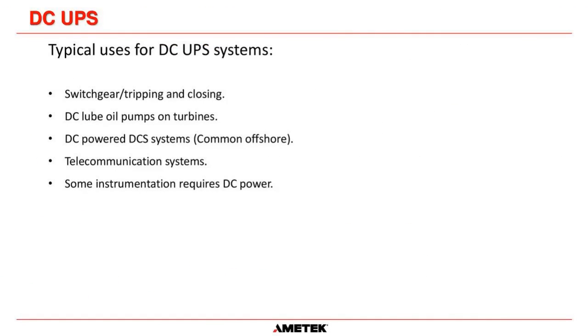So what are the typical uses for DC UPS systems? The typical uses are switchgear tripping and closing supplies. Obviously, that's your main MCCs. All of those MCCs have springs and coils that open and close the breakers automatically. So you need battery power to charge and discharge those springs if you lose AC power.